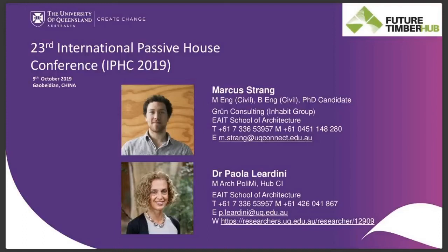Before we got to those, I actually had a question for yourself, Marcus. For the hygrothermal analysis, what software package did you use for that? I've been using WUFI Pro. Later, probably next year sometime, I'll also be using WUFI Plus to look at the building on a whole building level, to ensure that I'm taking into consideration the amount of moisture that's diffusing and the load that's required to dehumidify the latent energy loads as well.